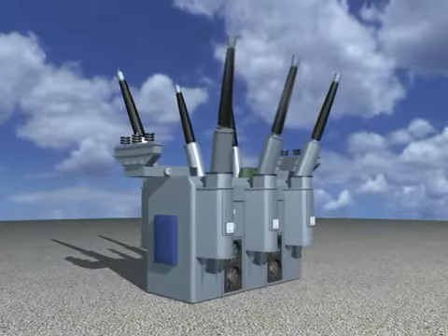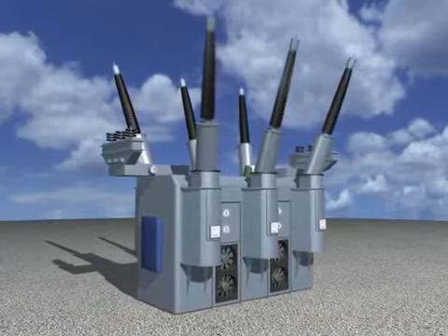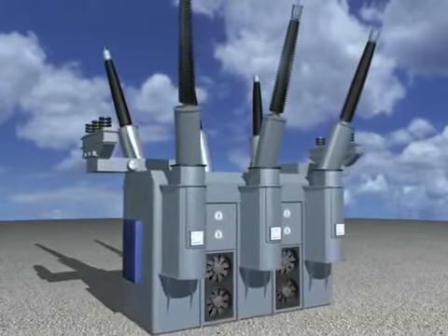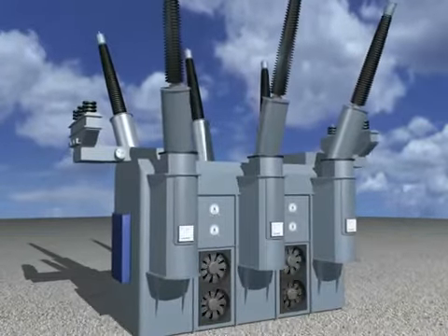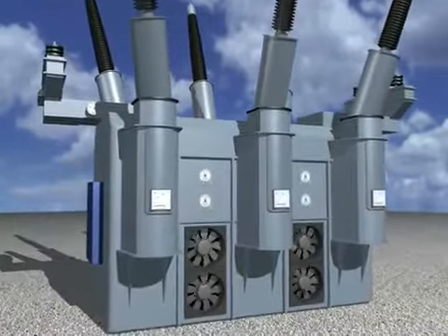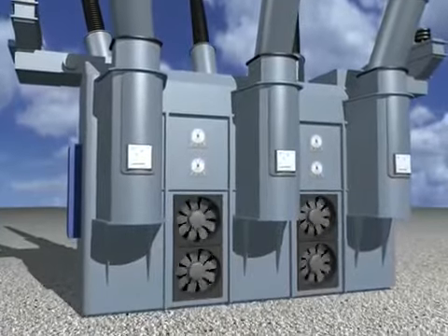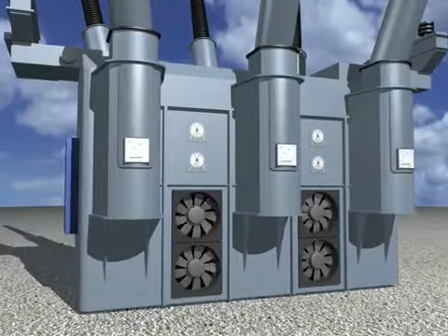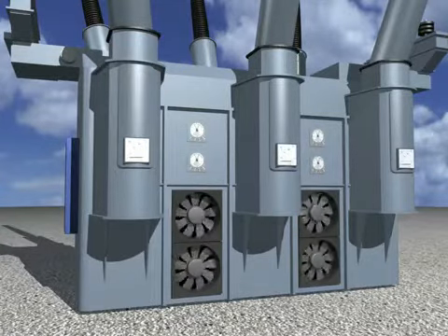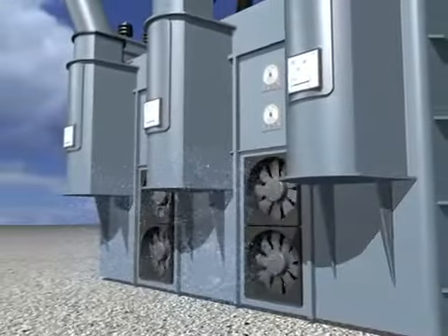Imprecise temperature monitoring can cause hot spots in some transformer applications and unnecessarily low load limits in others. Pumps and fans which run even when they are not needed cause an unnecessary high amount of wear. In the worst-case scenario, they must be completely replaced. The load-dependent temperature monitoring of the MTech system controls transformer temperatures within the required limits and simultaneously reduces fan and pump operation to an absolute minimum.